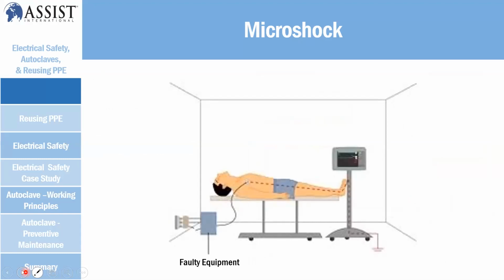One of the equipment, for example an ECG device, has a fault on grounding, or maybe you don't have a proper grounding line. So there may be a leakage on your faulty equipment. It's going to look for a new ground path. So it's going to go through that particular ECG line near your heart and find a new ground, through a contact of lower resistance. So the flow goes through the body. From the faulty equipment you can see the cable going to the body, and from the body it goes to the ground line.